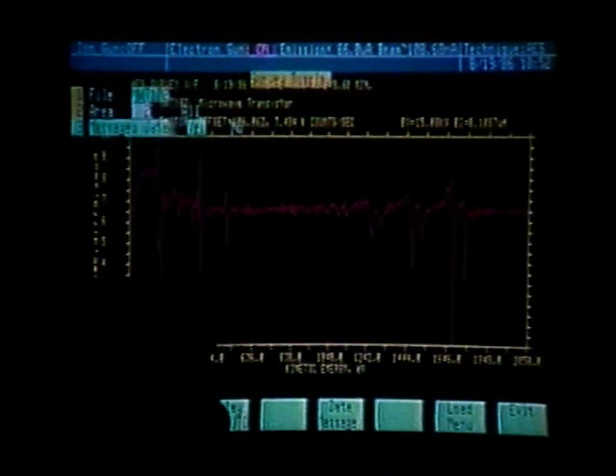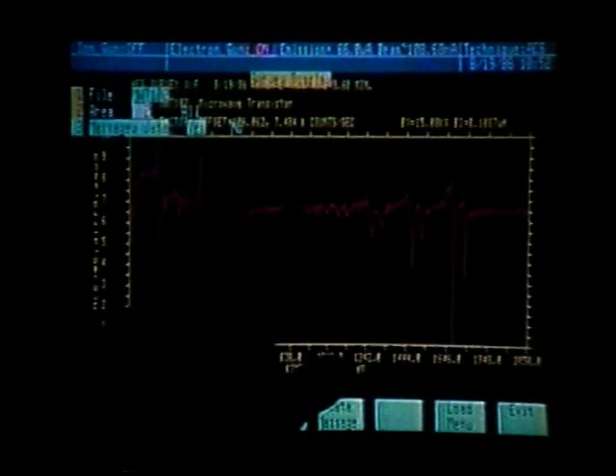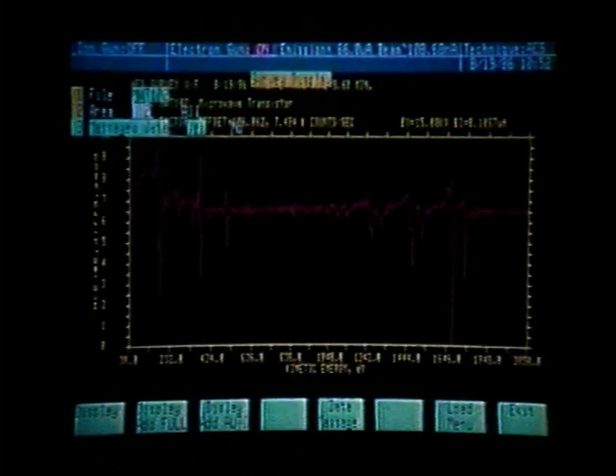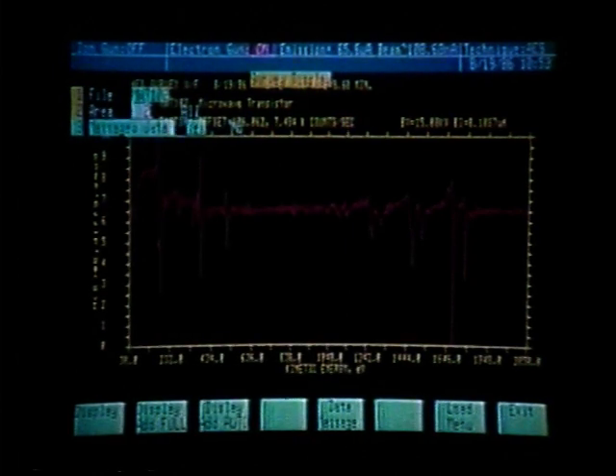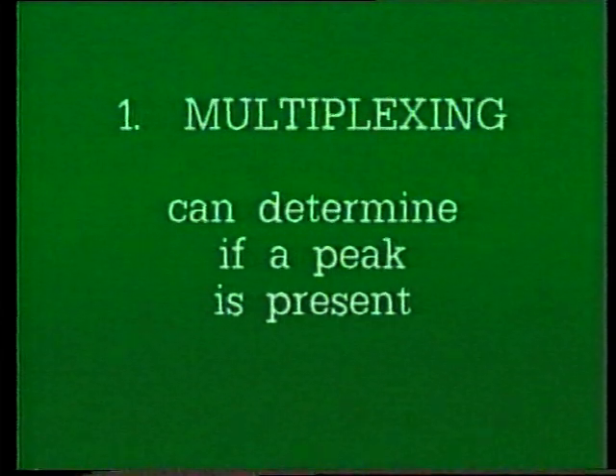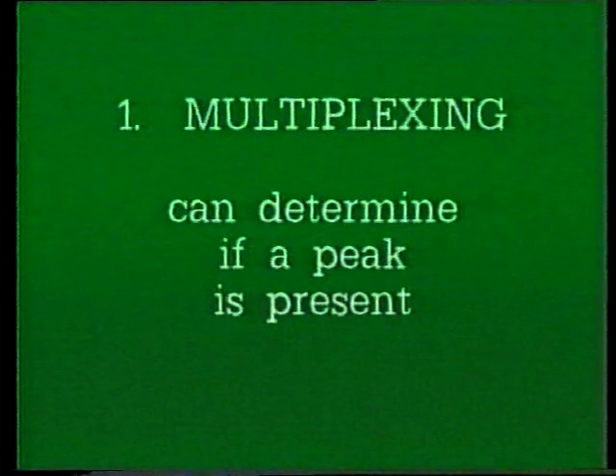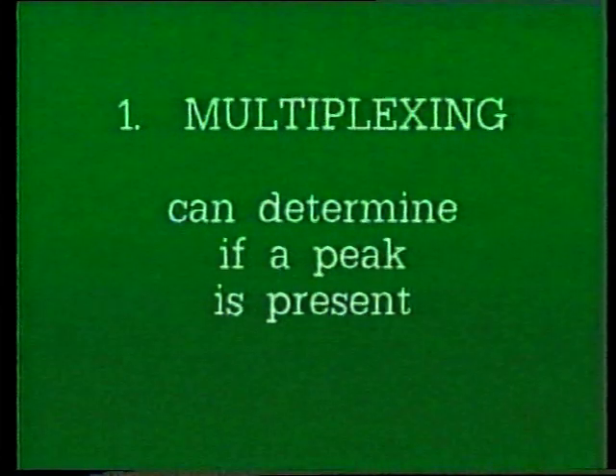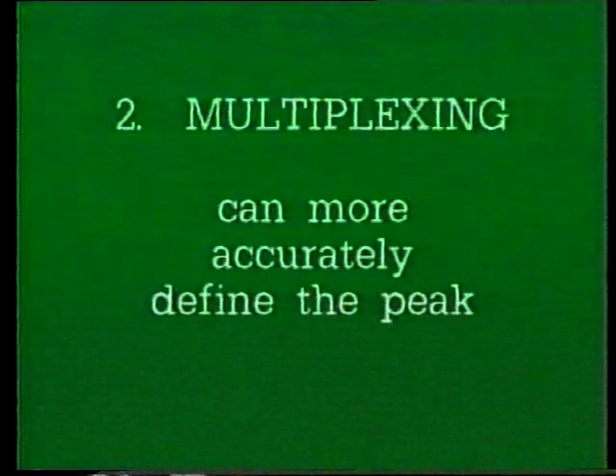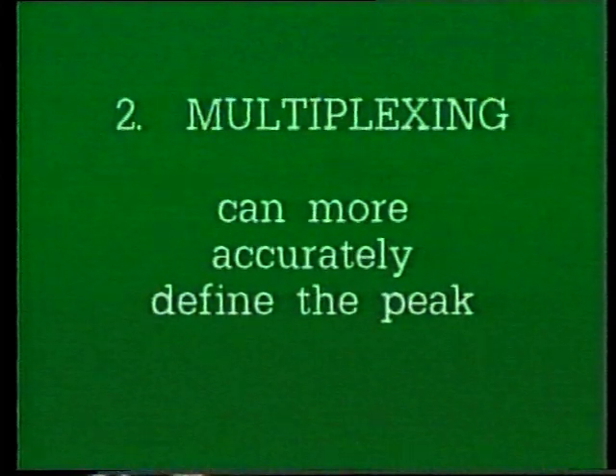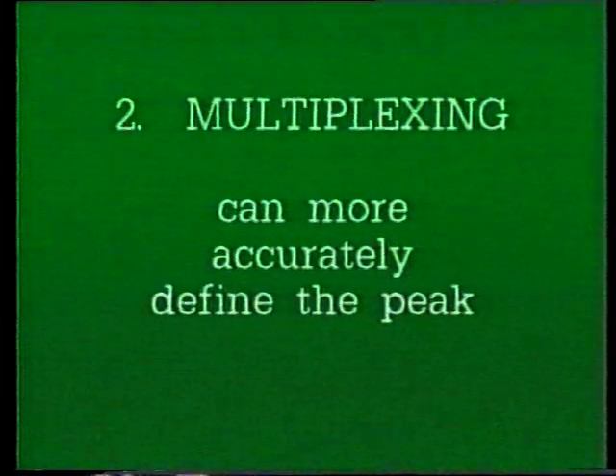What multiplexing can do is, if we thought that we had a peak in this area, we could set up a smaller range, just a window, and spend the same amount of time as it takes to do a survey scan, where we would get much better signal to noise because we would be spending that time acquiring data and signal averaging in a smaller area. That is one function of multiplexing — to look in a short range and determine in the same or less time whether a peak is there or not.